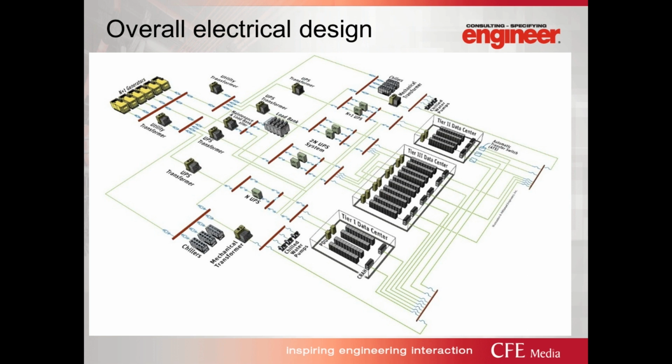And depending on the type of data center, that may be a huge deal or not. If it's a private enterprise and you want to agree with yourself that you're going to have an elevated risk to go ahead and do this, fantastic. If it's a high performance compute facility that is not going to be negatively impacted with a service level agreement to do that, fantastic. I think co-location facilities, hyperscale facilities are a lot less tolerant to these sorts of things, and great care needs to be taken to think about how you're going to add on to your infrastructure with zero downtime and mitigate risk as much as possible.